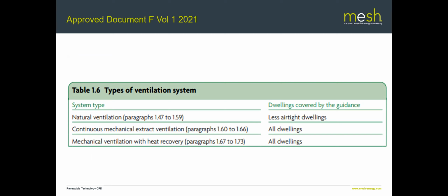So one of the biggest changes, and this is going to be quite an interesting one for architects, is that natural ventilation is now only considered suitable and covered in the guidance for what's defined as a less airtight dwelling. Now, bearing in mind what we were talking about at the start, about building an airtight dwelling being a good thing, that means that for an awful lot of buildings that we're designing now, we're not going to be able to use natural ventilation and stick within what ADF tells us to do. The other 2 systems, continuous mechanical extract and MVHR, are suitable for all dwellings.